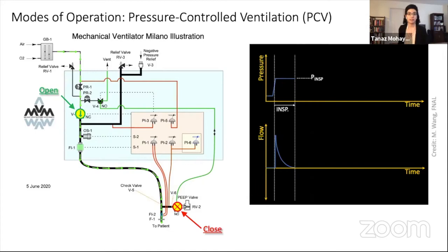In PCV mode, the air that the ventilator flows into the lungs generates a preset positive pressure for a preset time. You can set the respiratory rate - the number of breaths per minute. You can set the PEEP. You can set the ratio of inspiratory to expiratory time, which indicates how long the inspiratory phase should be compared with the expiratory phase. Looking at the waveforms, as the ventilator starts the inhalation cycle, we see a high rate of volume delivered to the lungs, as shown in the flow versus time waveform at the bottom.